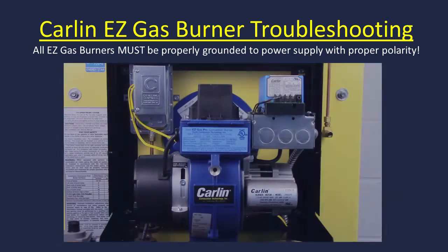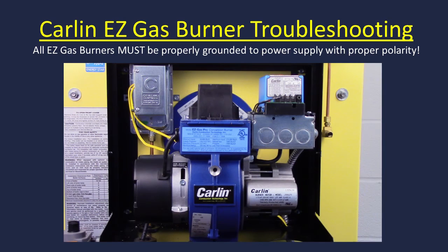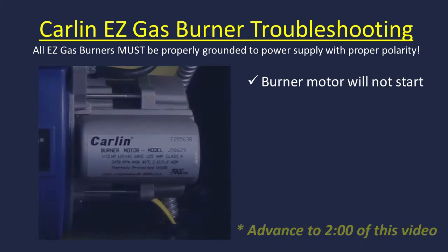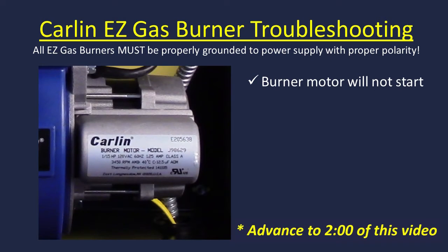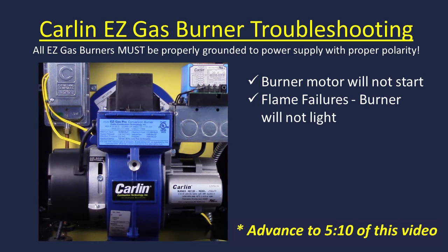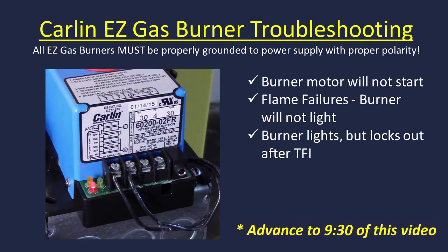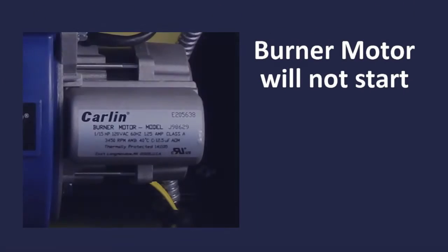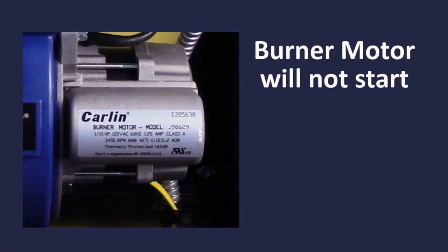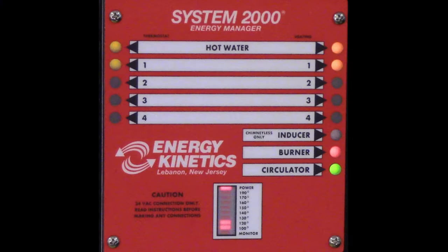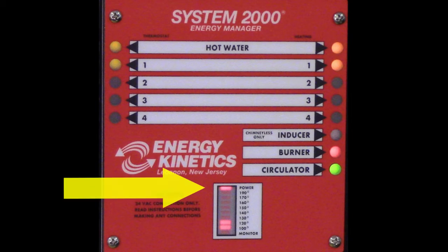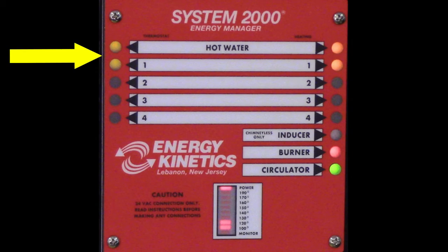This video will help guide you through some of the common causes and solutions relating to the EZ Gas burner motor not starting, the burner not lighting, and the burner lighting but locking out after trial for ignition. If the burner motor won't start, begin by confirming that the digital manager power light is on and there is a thermostat call for heat or hot water.